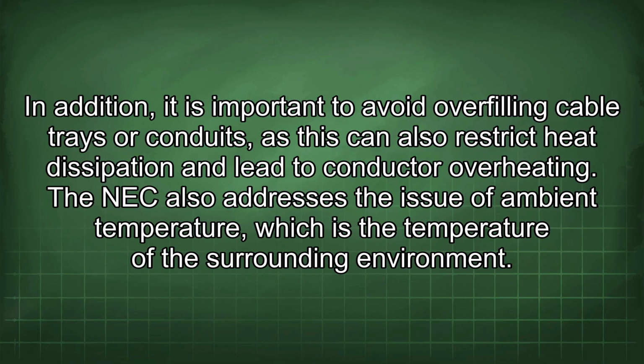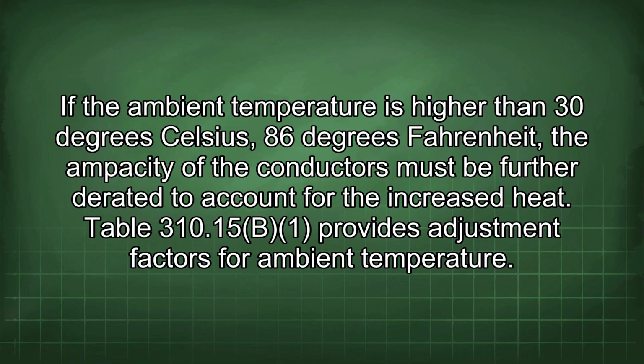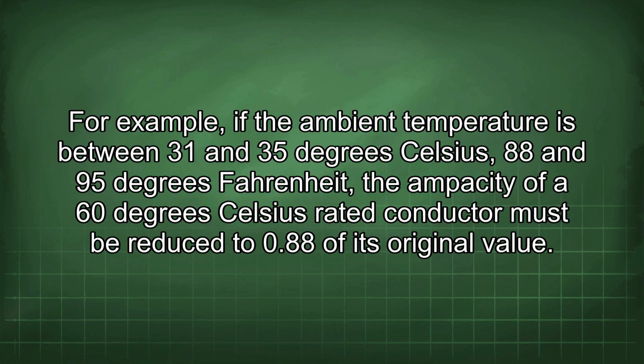The NEC also addresses the issue of ambient temperature, which is the temperature of the surrounding environment. If the ambient temperature is higher than 30 degrees Celsius, 86 degrees Fahrenheit, the ampacity of the conductors must be further derated to account for the increased heat. Table 310.15 provides adjustment factors for ambient temperature. For example, if the ambient temperature is between 31 and 35 degrees Celsius, 88 and 95 degrees Fahrenheit, the ampacity of a 60 degrees Celsius rated conductor must be reduced to 0.88 of its original value.